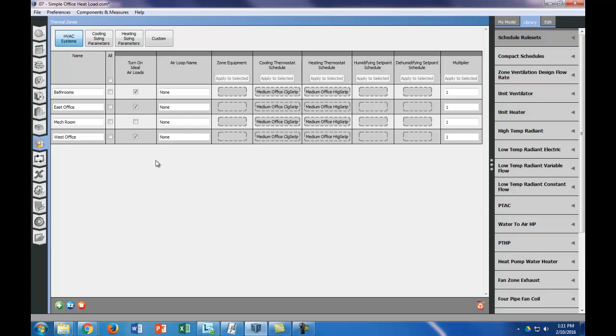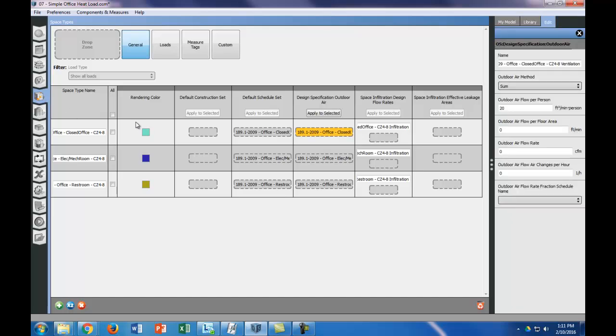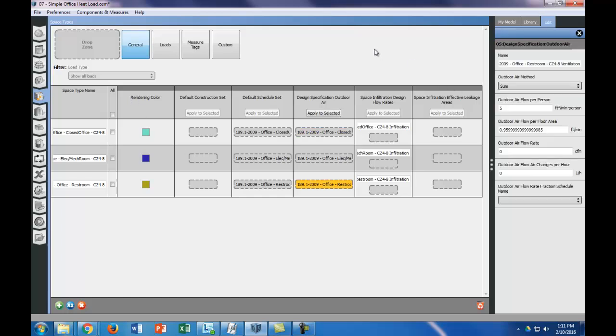The next thing we're going to do is we're only going to bring in 5 CFM per person in our example. So we're going to go to our space types here, and we're going to change the outdoor air flow per person to 5 cubic feet per minute per person. And you can see that we're going to do that for all of our spaces. The other thing to notice is that in the office, there's no outdoor air flow per floor area, but in the restroom there is. So that's just to ventilate the restroom, since we want to bring in fresh air to the restroom.